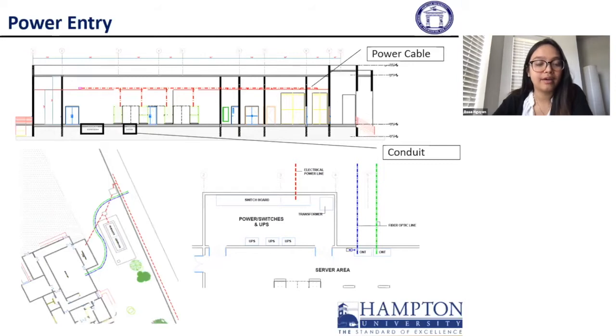For power entry: in the sectional diagram, the power cables shown as red dotted lines run overhead and are accessed by ladders, while conduit at the bottom is where power enters from the utility transmission. Looking at the bottom-left picture, the red line runs along the sidewalk of that lot — the power lines are actually along the sidewalk, making it fairly easy to tap into. We wouldn't need major power construction on the site. The bottom-right diagram shows the electrical power line going into the switchboard. In the power room we have one main switchboard — since it's an ABB smart panel, we can just add on to it. It has a smaller dimension compared to older switchboards. The transformer sitting in the corner is a dry type, more beneficial for a smaller facility like ours. We have three UPS systems lined up against the wall, with the hot-air vent on top of the cabinet allowing them to sit against the wall.